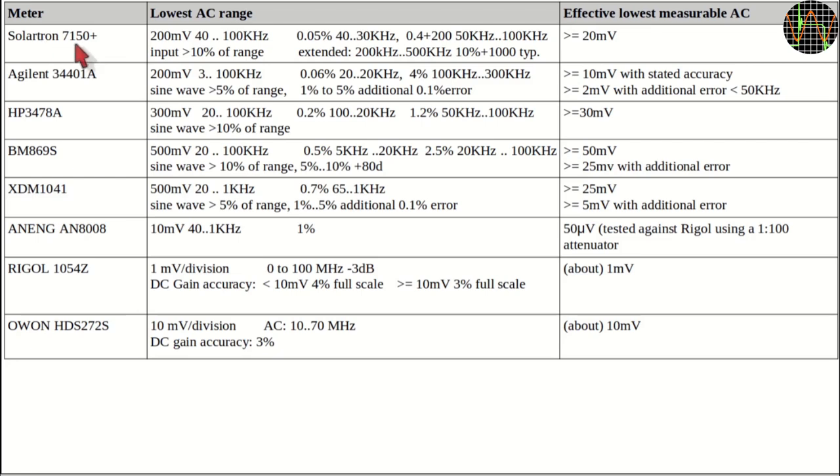Below that, your meter is just telling you nonsense. Hence, the Solartron 7150 Plus with its 200mV lowest AC range needs to see at least 20 mV, and if you go faster than 100 kHz, you pay with extra errors.